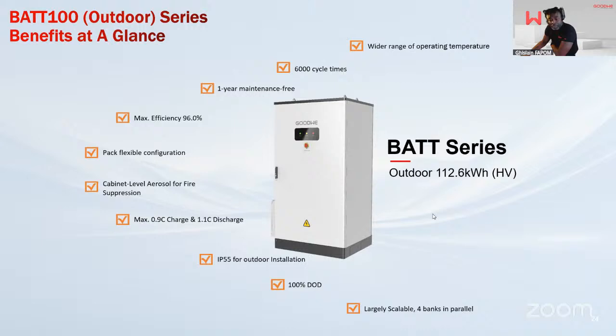It's IP55 outdoor. You also have temperature control, 100% DOD, and maximum efficiency of 96%. Most importantly, it's a 6,000 cycle, 70% end-of-life battery, with 1 year maintenance free, meaning that distributors can now keep this battery in their warehouse for up to a year without having to cycle it.